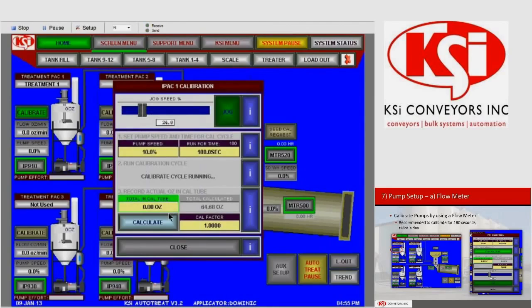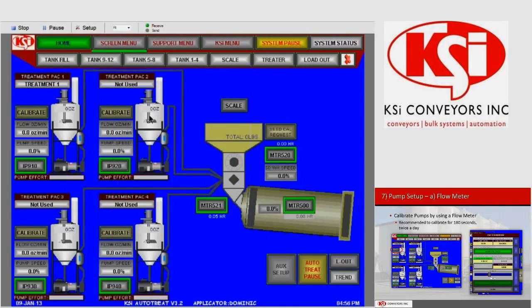And again, we want to make sure that we press calculate again. Don't close out at this point. We're not done. We need to press calculate, and this cal factor will change from something other than 1. Once we're done with this, we can close that window, and our treatment pack 1 is complete. We would do this calibrate process for all 4 or however many pumps we have on our site.